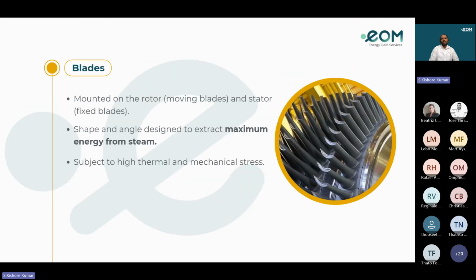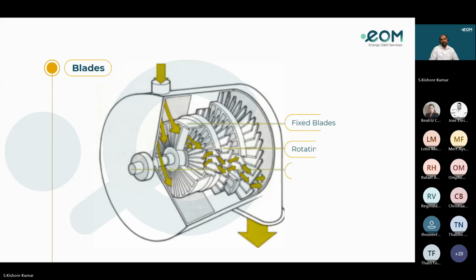Coming to the blades, there are moving blades on the rotor and stator or fixed blades. The shape and angle are designed to extract maximum energy from the steam. Being subjected to high thermal and mechanical stresses, the blades of the turbine have an airfoil shape. When the high energy fluid passes over the airfoil shape, it creates a pressure difference, which subsequently creates the lift force. Here we can see the moving or rotating blades, the stationary or fixed blades, and the flow pattern of the steam. The steam enters the turbine and passes through the stationary nozzles, then to the rotating blades, and it passes through the different stages of the blades, and goes to the exhaust of the turbine.